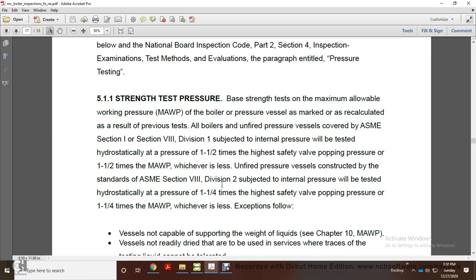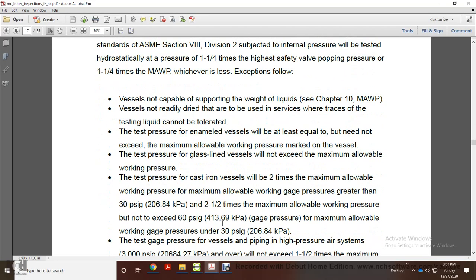Boilers and unfired pressure vessels that fall under ASME Section 1 or Section 8, Division 1, subject to internal pressure, will be hydrostatically tested at 1.5 times the highest safety valve popping pressure or 1.5 times the maximum allowable working pressure, whichever is less. Unfired pressure vessels constructed to ASME Section 8, Division 2, subject to internal pressure, are tested at 1.25 times the highest safety valve popping pressure or 1.25 times the maximum allowable working pressure, whichever is less. Exemptions.